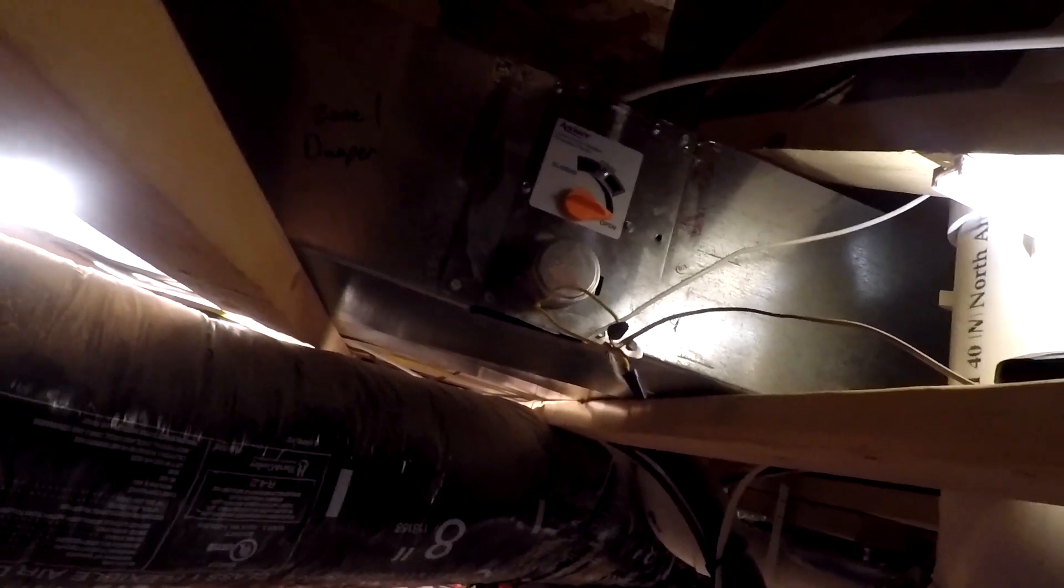There's that call for heat. Should be getting power to zone one. Should be getting power to this wire. That little motor should be starting to wind up. So there we go. Sorry for the camera change. My GoPro died. Just more evidence that I'm not a YouTube guy. It's my first fix-it video, but hopefully this one is helpful to you. If it's still not working, check your connections. Make sure you have good connections to your power lines as well as your motor lines. Check the motor, see if it's spinning.